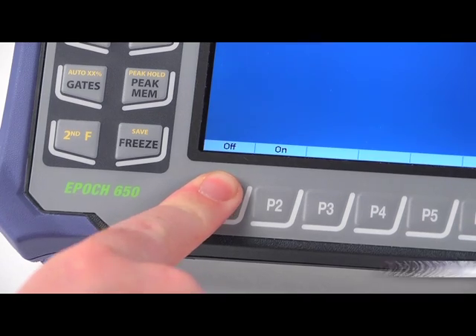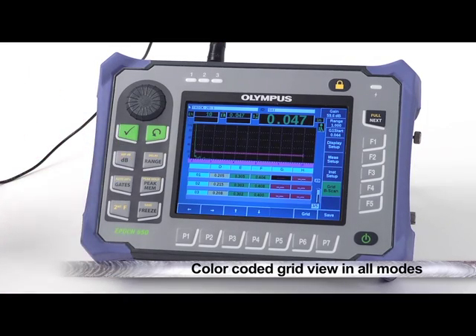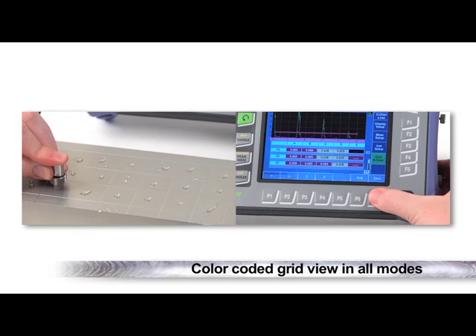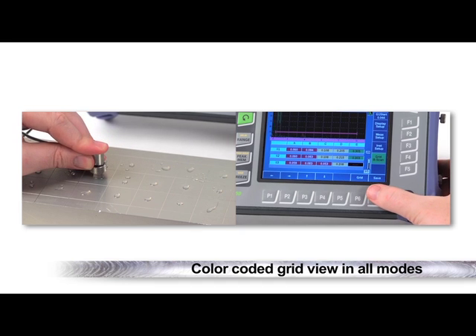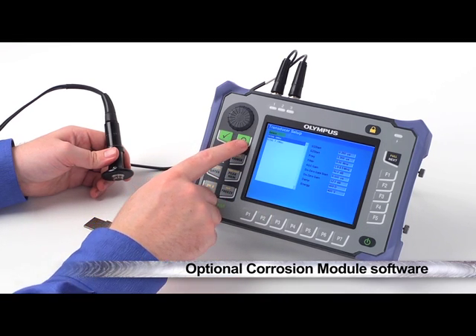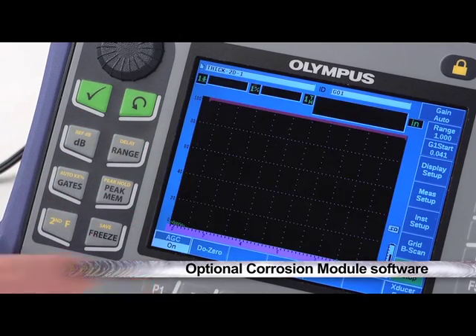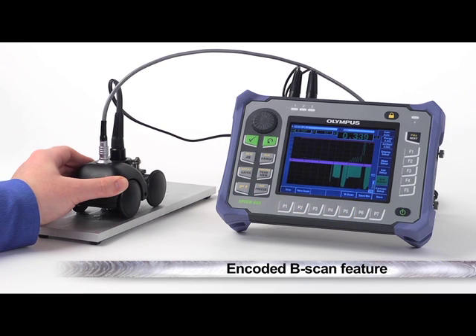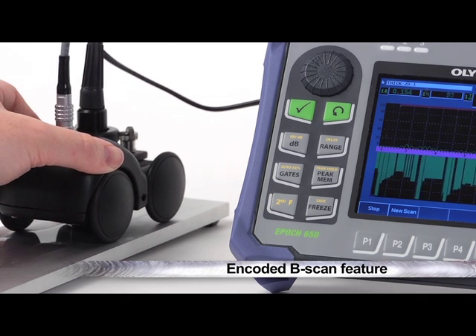The EPOCH 650 offers a standard color-coded grid view feature in all modes. This feature can be used for corrosion inspections, but can also be used during single crystal inspections for quality control and other data collection surveys. Optional corrosion module software is also available to increase the setup speed, ease of use, and measurement precision of corrosion erosion inspections. Rapid part screening and defect reporting is enhanced in this mode by an encoded B-scan feature.